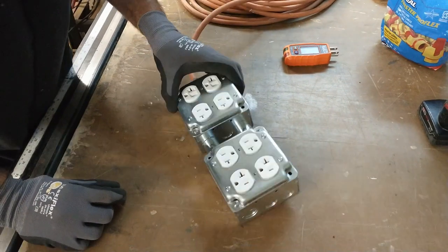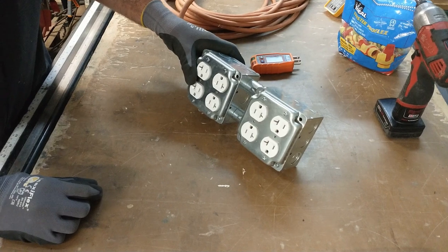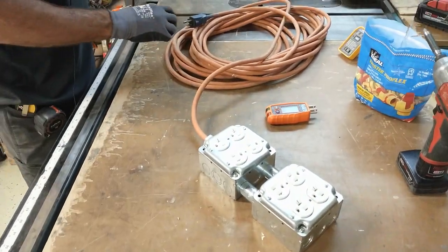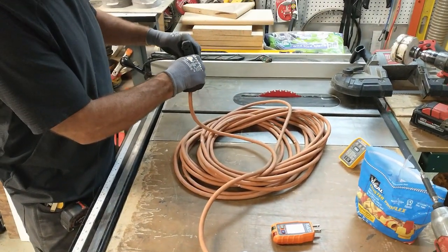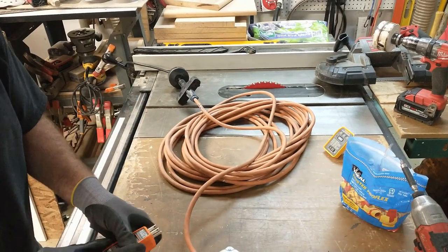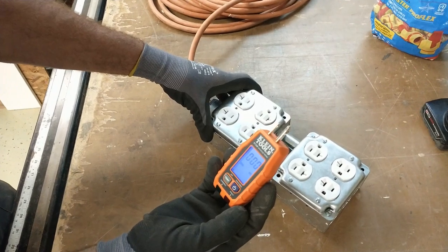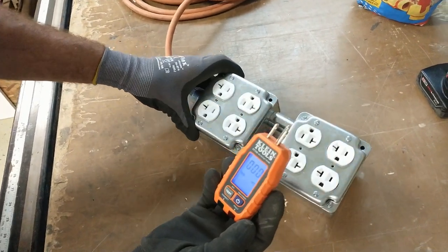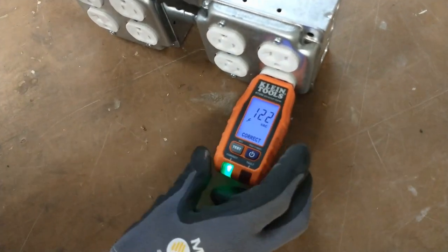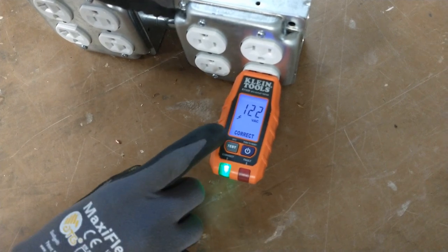So we're ready to plug this thing in and test it to see if all of our receptacles are wired correctly. I'm going to go ahead and plug in the cord — it's now hot. I'm plugging in a Klein plug tester with a digital readout.